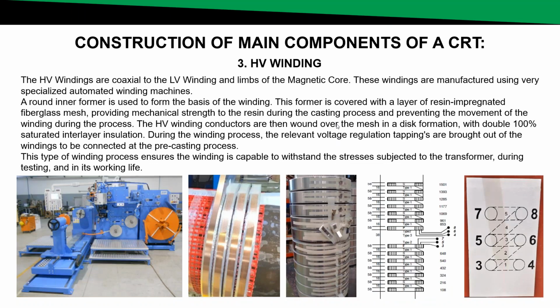Let's have a look at the HV winding. The HV windings are coaxial to the LV windings and limb of the magnetic cores. These windings are manufactured using very specialized and automated winding machines. The HV windings are also usually round in shape, and a round former is used to form the base of the HV winding. The former is usually covered with a layer of resin impregnated fiberglass mesh, providing mechanical strength to the resin during the casting process and preventing the movement of the winding during the process.